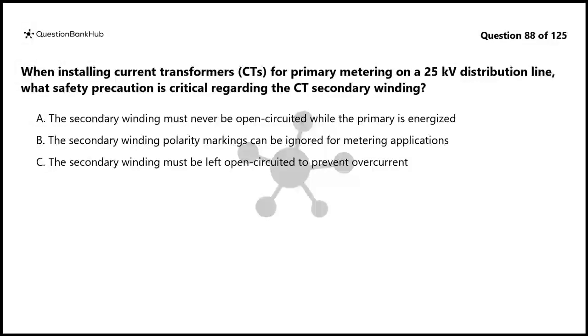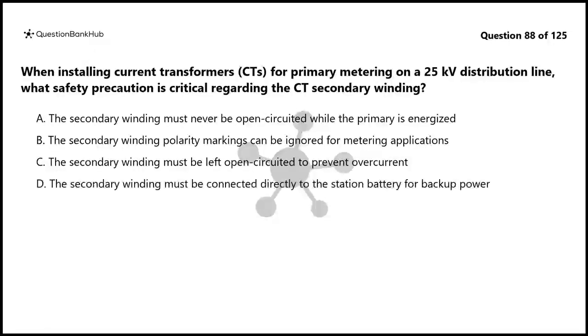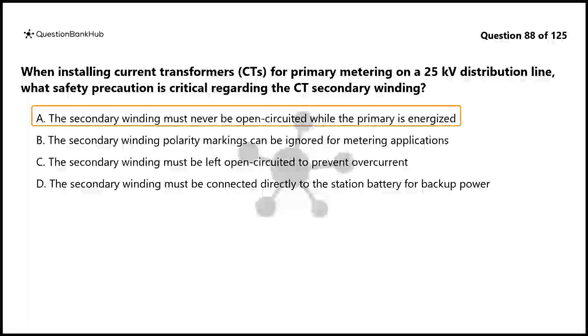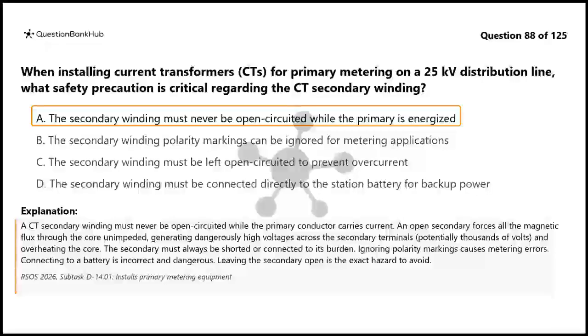C. The secondary winding must be left open-circuited to prevent overcurrent. D. The secondary winding must be connected directly to the station battery for backup power. The correct answer is A. A CT secondary winding must never be open-circuited while the primary conductor carries current.